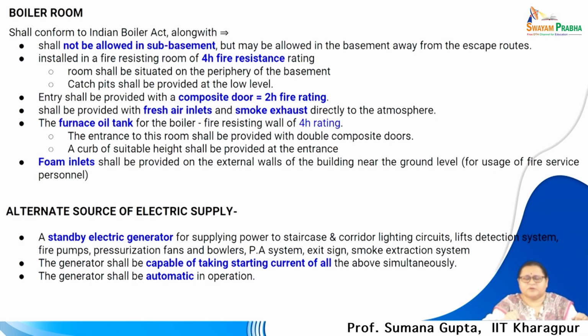Boiler rooms, hot water supply. If your high rise building has water requirements, it may have boiler rooms, which should be 2 hour minimum fire rated on all sides. If it is installed in a fire resisting room, it should be mandated that it has 4 hour fire resistance, and there should be fresh air inlet and smoke exhaust separately added to these kinds of rooms.